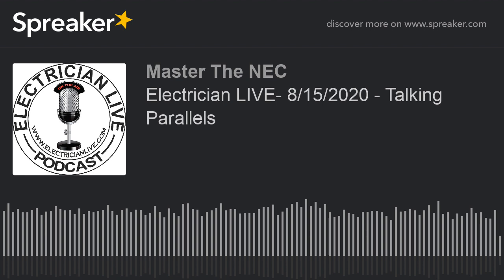Now, here's what people say to me all the time then. So what about that equipment grounding conductor? Because I have some images. Actually, I did a graphic that I sent in with my public input that shows 3 sets or 5 sets, or whatever it was. The equipment grounds were terminated identically on 3 of them, and then the 4th one went over to a separate lug that was bolted onto the enclosure. And everybody, people that I talked to, joking with them, they go, no, it's not terminated with the same characteristics in the same way. And I said, well, yeah, it does, but the problem is it does say equipment grounding conductor and equipment bonding conductor up here. But why does it have to be terminated the same?